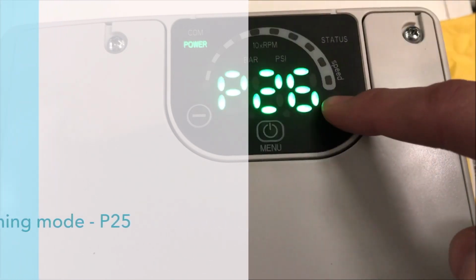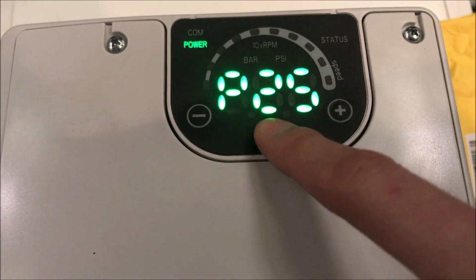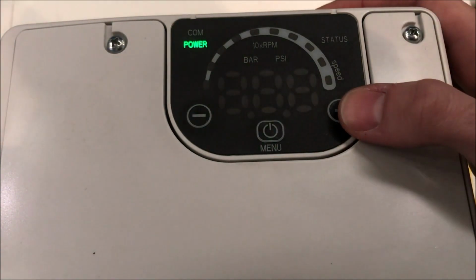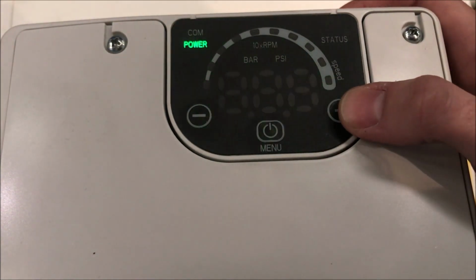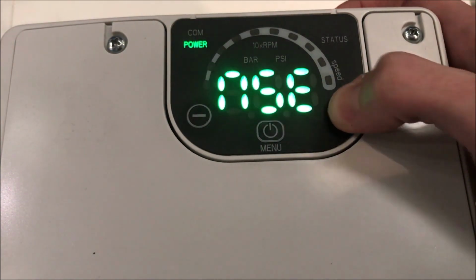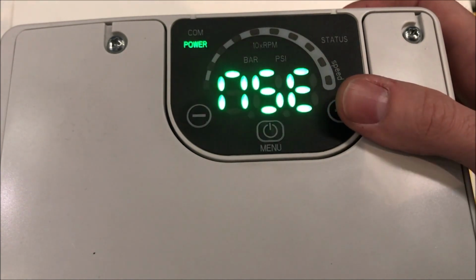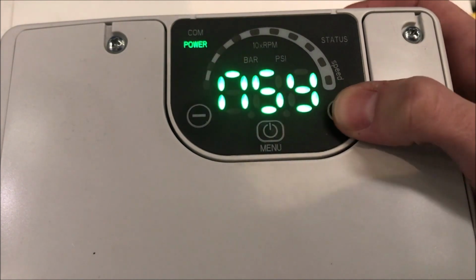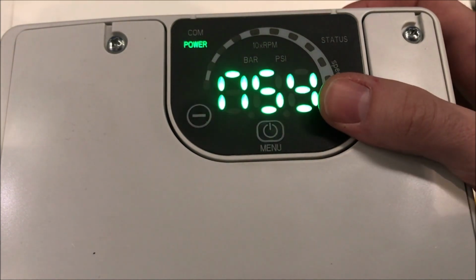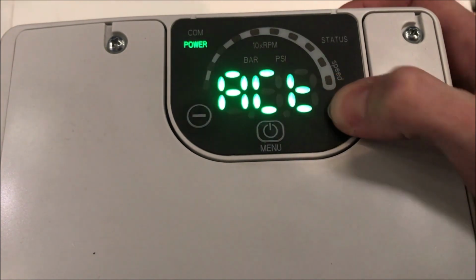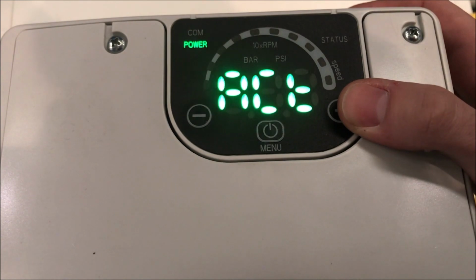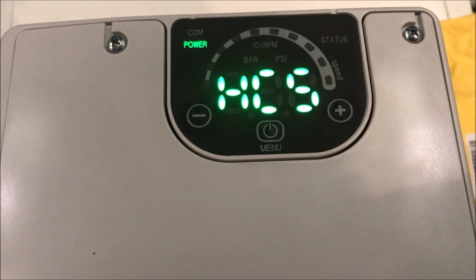The mode of the ESM drive can be changed in parameter 25. HVAC controller mode for single pump use. Multiple pump mode in serial cascade. Multiple pump mode in synchronous cascade. And actuator mode when using an external 0 to 10 volt signal.